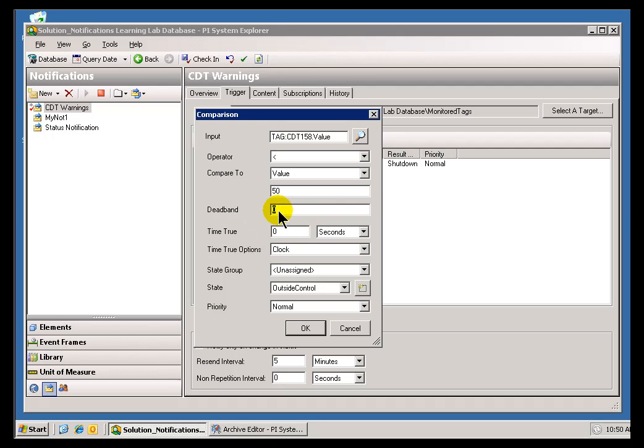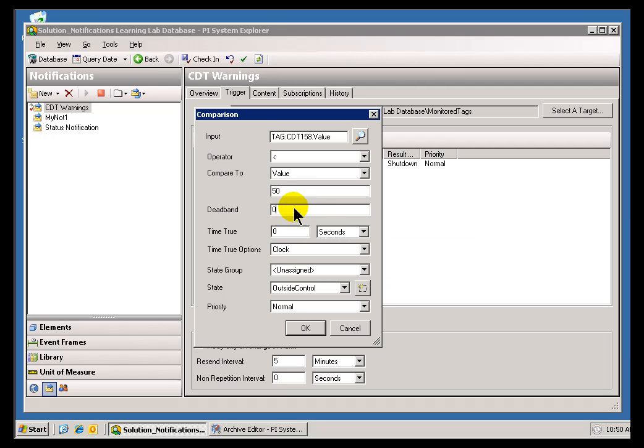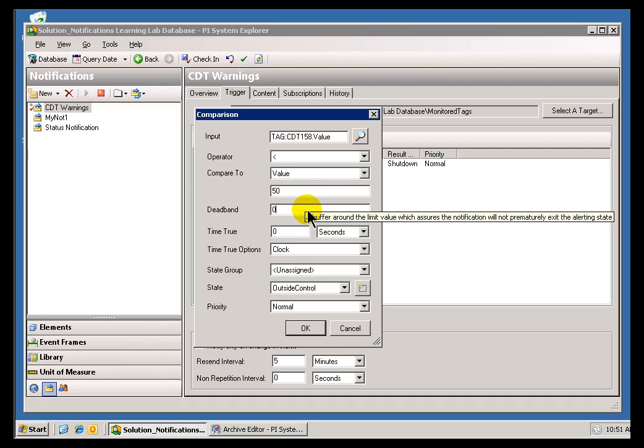Let's go over some of these other things, like Deadband. When you specify a Deadband, what you're doing essentially is trying to avoid the kind of toggling in and out of an Alarm State that you might get if you've got something that's right on a border going just above and below 50 over and over again.